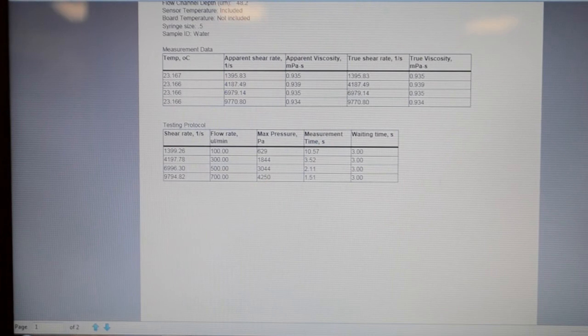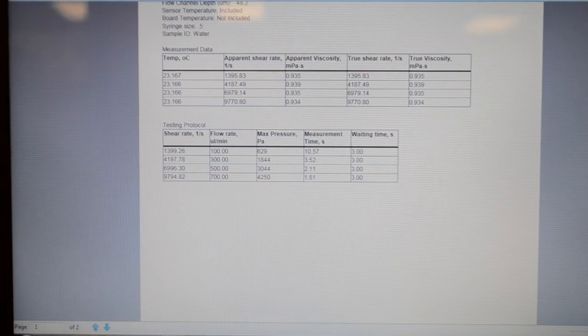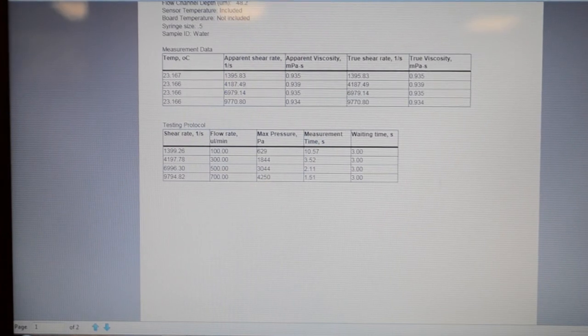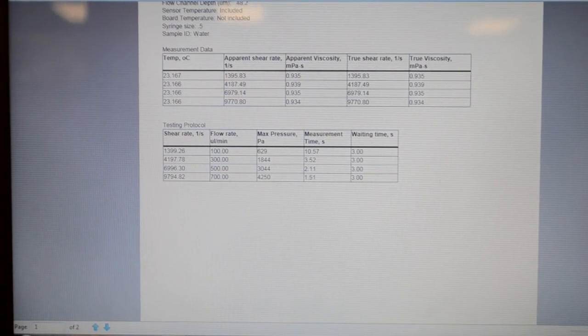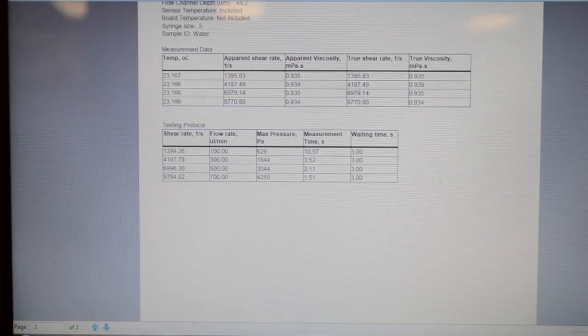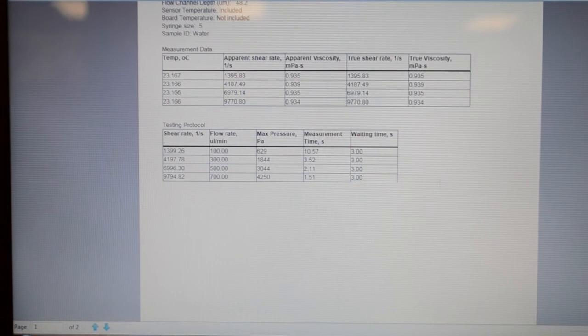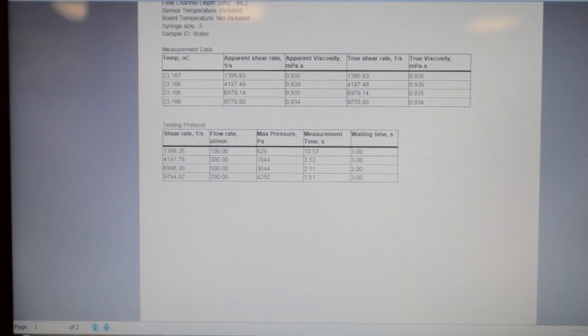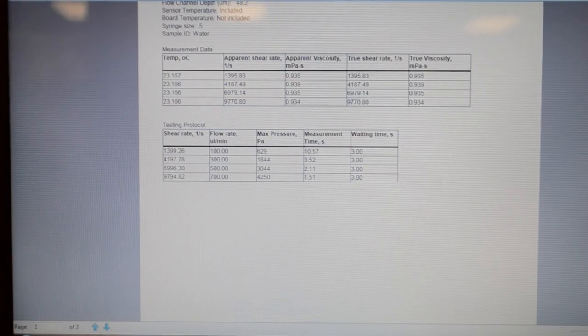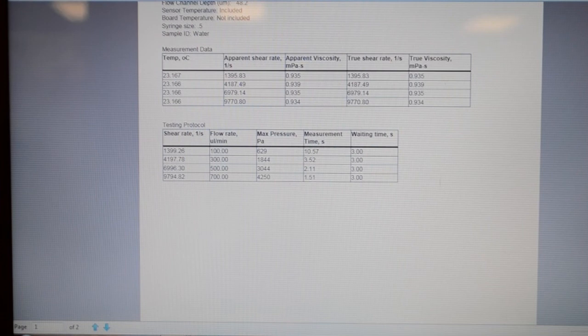This demo was done without temperature control. With additional temperature control, this protocol should yield accurate viscosity measurements within 2% of the true value.